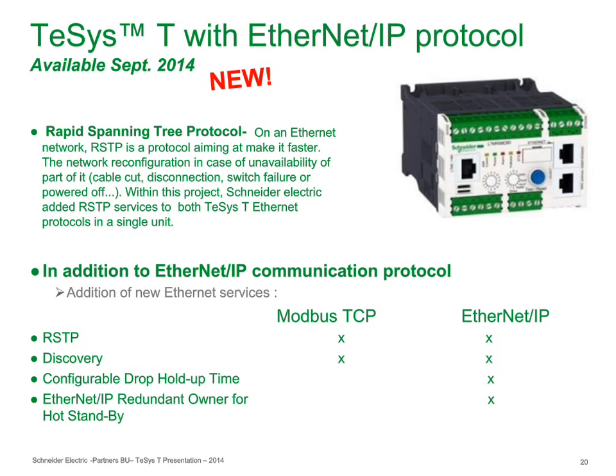So if we have any situation where we have a break in the cable or in the communication here, rapid spanning tree protocol will actually allow us to, within less than 1 second from another supply point, basically pick up that device from a different direction. So this is very, very useful for us because we can not only do warm standby, but we can actually do hot standby capabilities now with this device using the Ethernet IP protocol with the rapid spanning tree protocol that goes along with it.